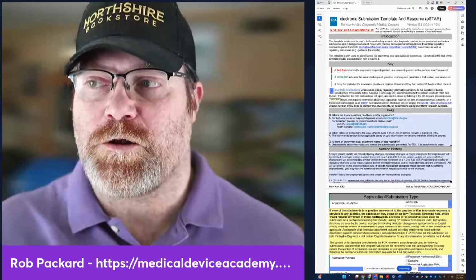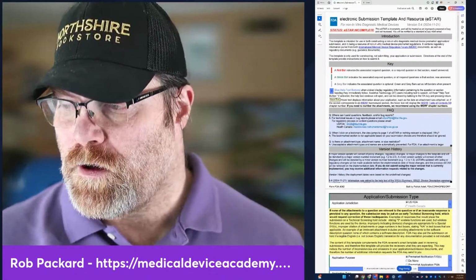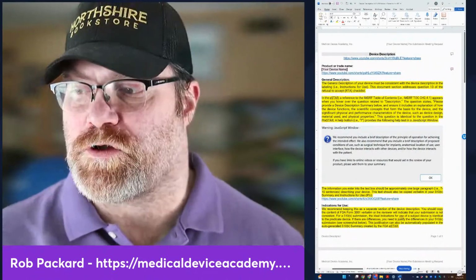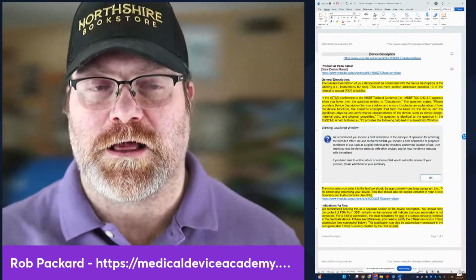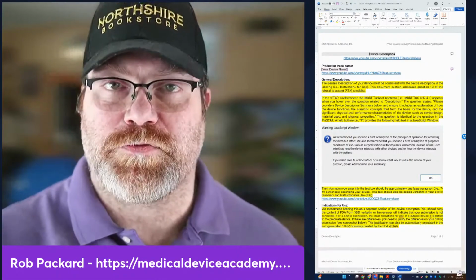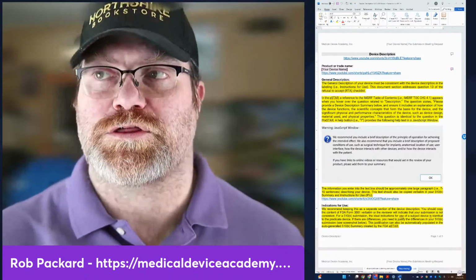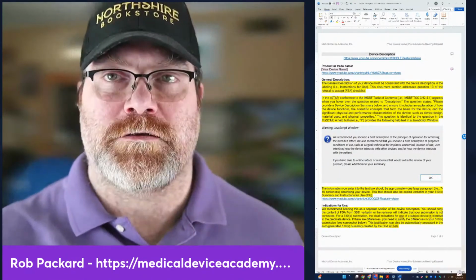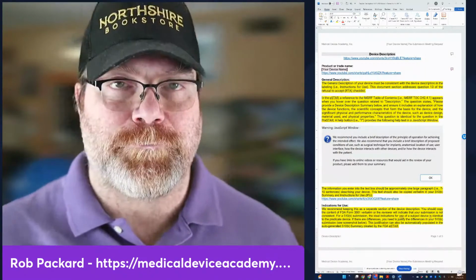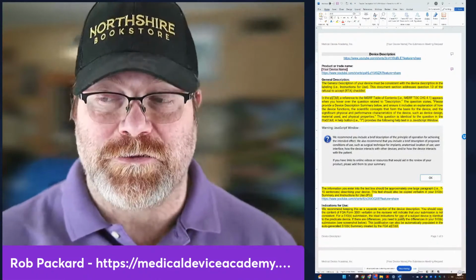So I'm going to walk you through the changes that we've made, but I'm also going to share with you our template for a device description. So here's our template for the device description. And this is what we send all clients that we're going to be starting a new project with, whether it's a pre-sub, it's a breakthrough device designation, it's a 513G, whatever it is, we always start with this. And we have a separate one that we use for IVDs that's a little bit different. But in here, we give hyperlinks that show people where to find additional training on how to fill this in.